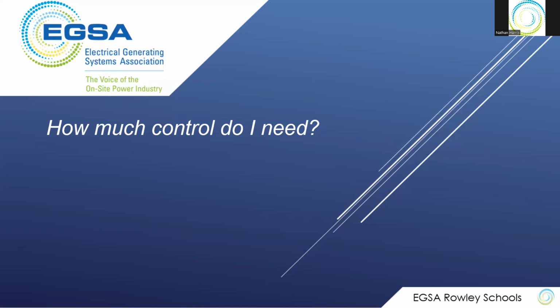How does galvanic isolation relate to the system? The control system should be galvanically isolated to system ground, okay? The galvanic isolation, let's take, for example, the older analog load share lines were 3 volts, plus or minus 3 volts. You would use those lines to balance load between control systems. If the ground at one point was different than the ground at the other point, even if it was just only during transient conditions, that ground potential would be different, that 3 volts would be different. And so you might end up with forcing the generator on harder than the other one, because it would see that difference in that voltage.